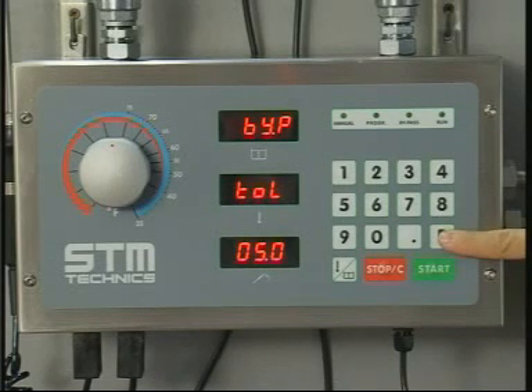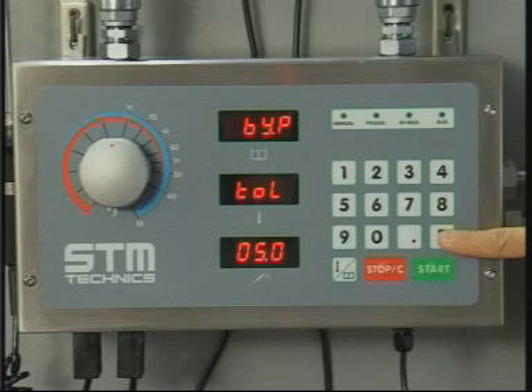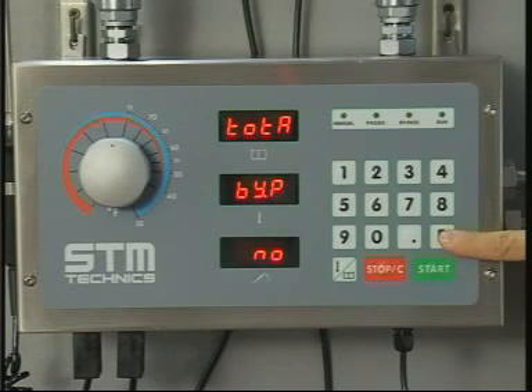BYP TOL. This display appears if in the previous option the temperature control for the bypass has been chosen. The tolerance of the intervention of the bypass is given in degrees. The set degrees will be referred to the unit of measure selected before. If instead of temperature, time control is chosen, the display will be BYP SEC and the length of time is shown in seconds. Total BYP.